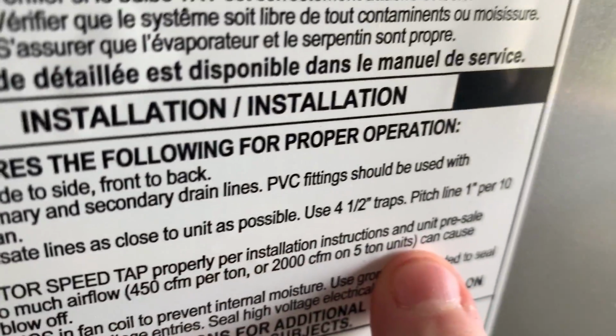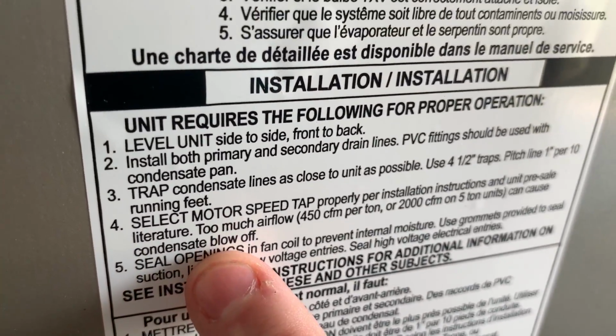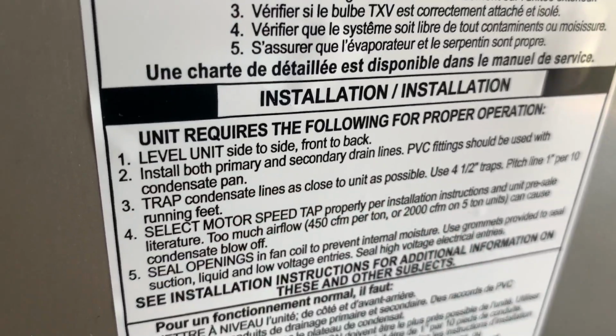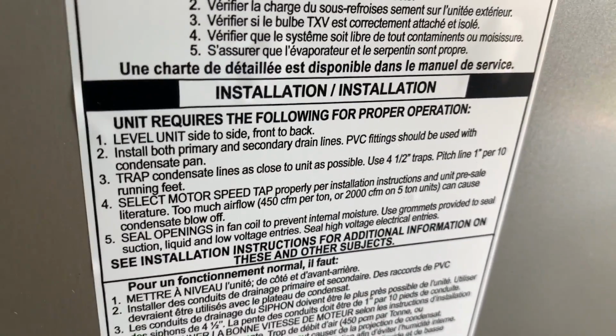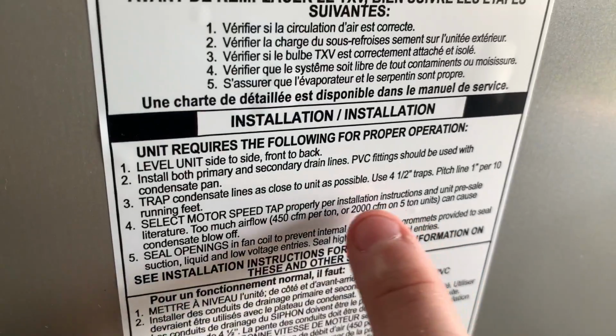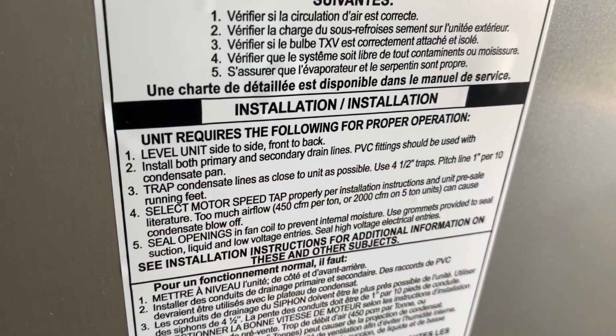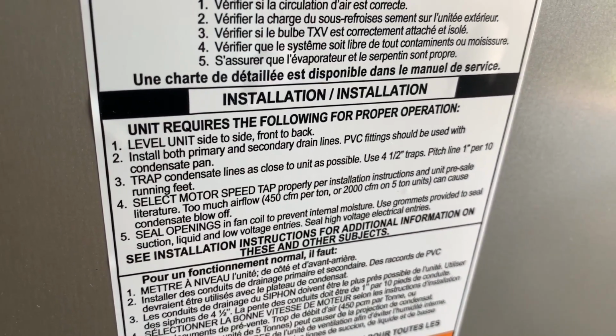You can see here, too much airflow can actually cause high velocity and can actually cause condensate blow off on this specific brand. So we set it to 350 CFM per ton in Florida in order to optimize dehumidification, but you can actually get condensate blow off if you have too high of airflow.